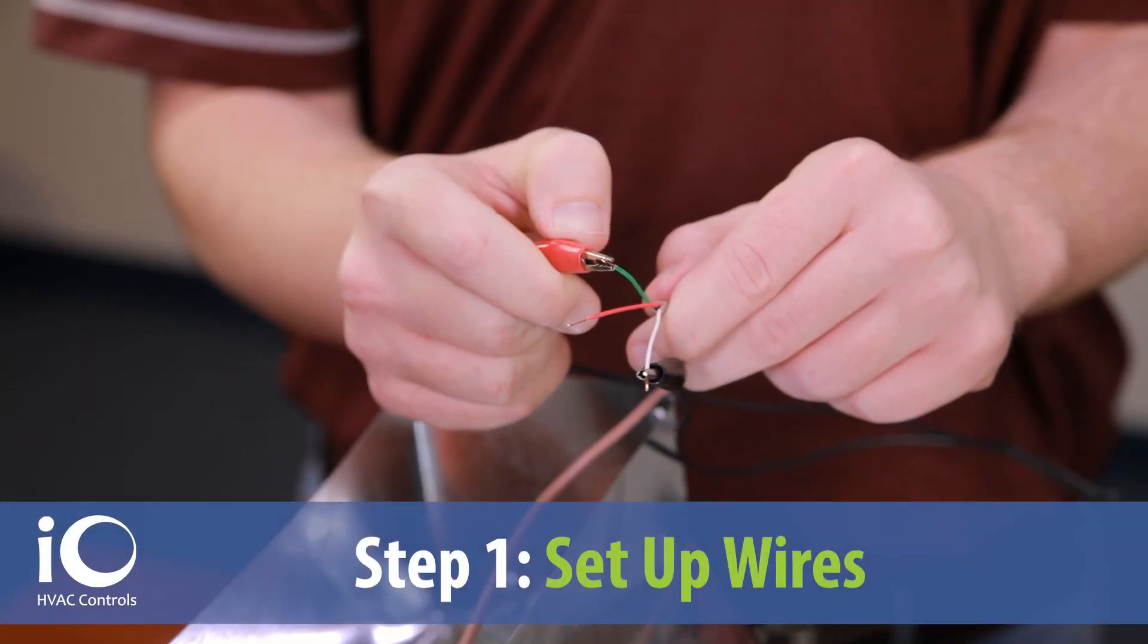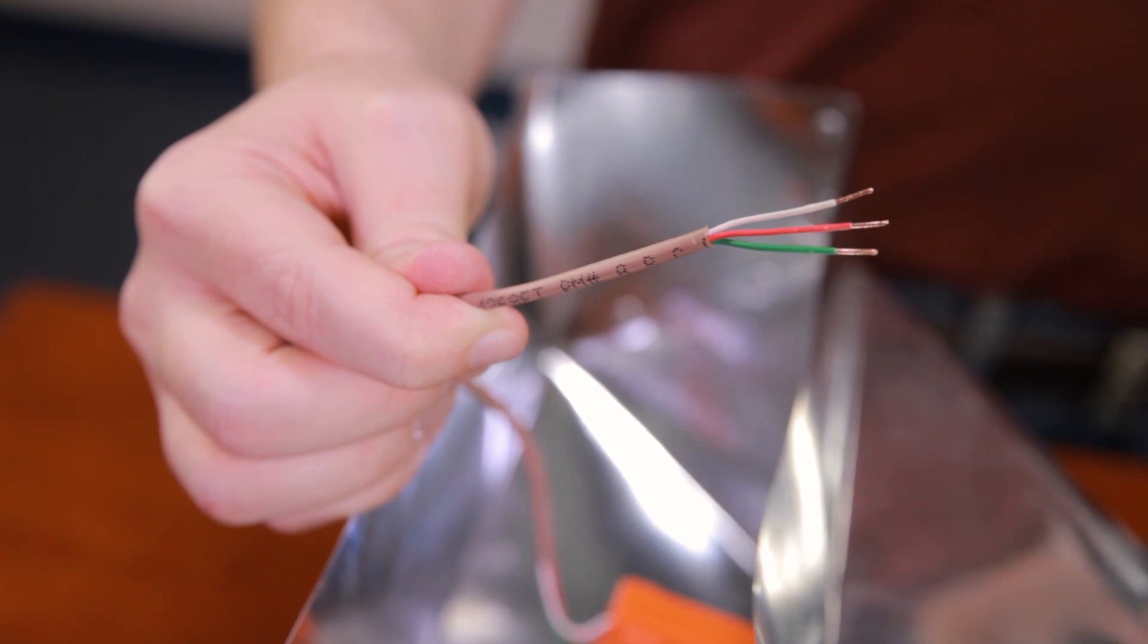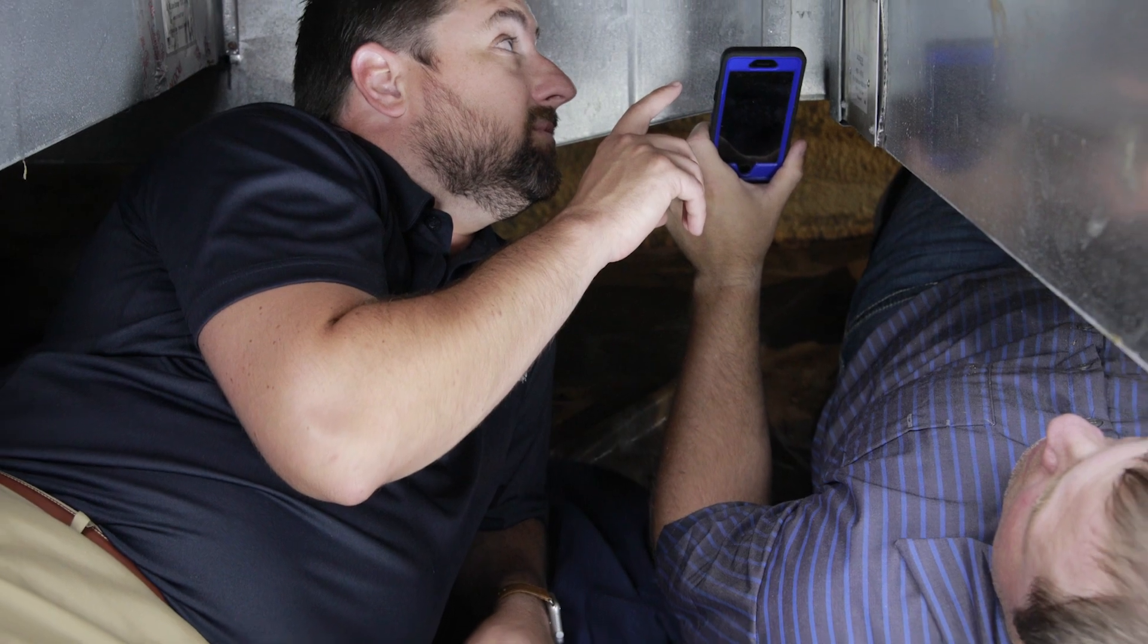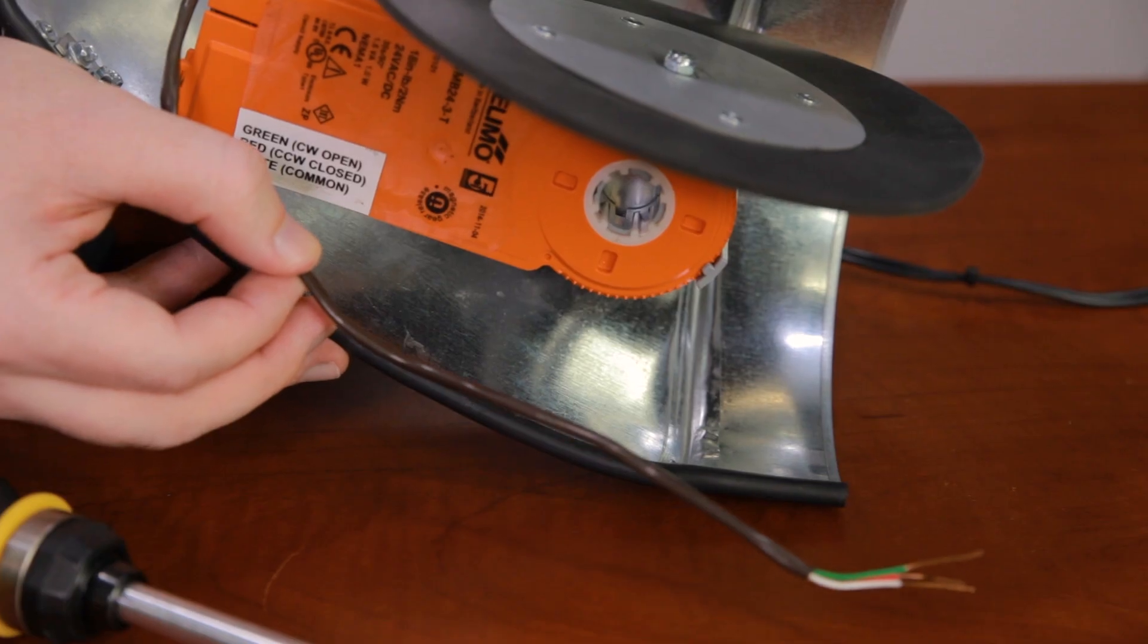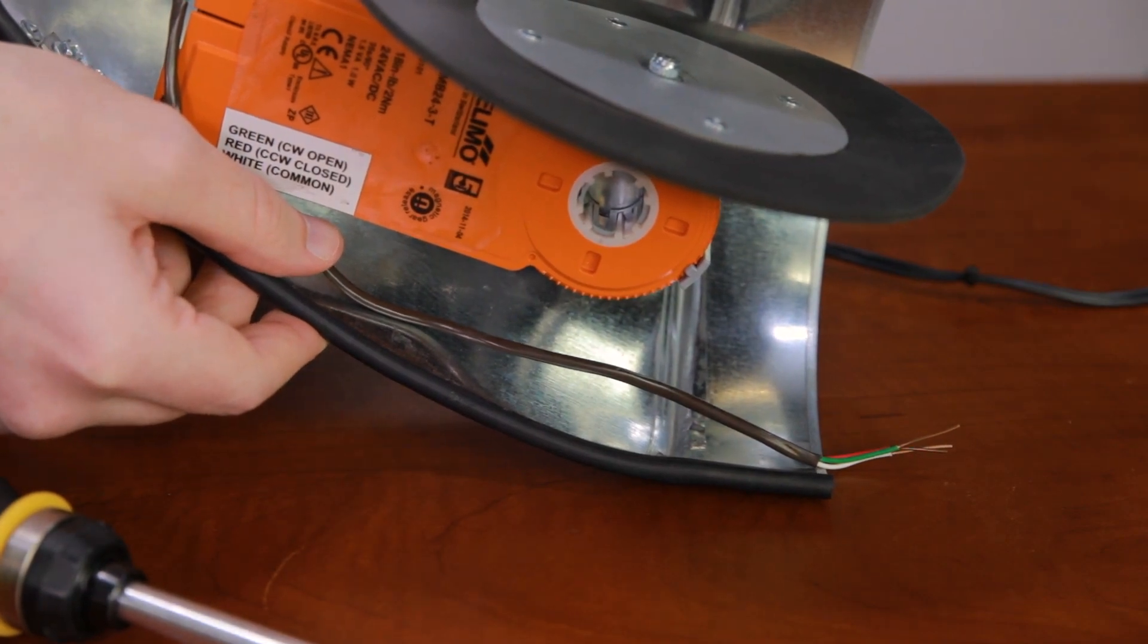Step 1. The register boot damper is powered by 24 volts AC. 18-3 thermostat wire is recommended. Wire not included. When possible, run the wire through the crawl space or a chase. If not available, run wire through ductwork. Plenum rated wire is highly recommended.